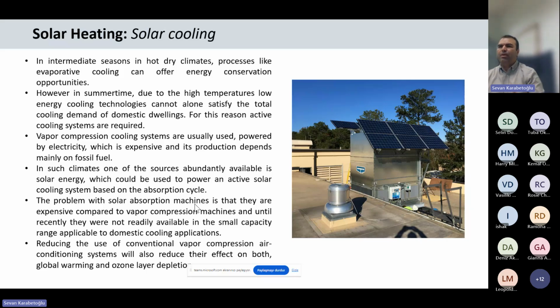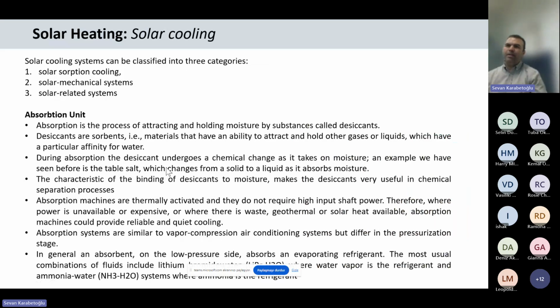Therefore, we can decrease the consumption of electricity for vapor compression, and the COP values for refrigeration will be higher by using these solar collectors. So, of course, reducing conventional vapor compression also reduces the effect of global warming and ozone layer depletion. So economically and environmentally it is a better solution. There are three types of solar cooling: solar absorption, solar mechanical, and solar related systems, but we will focus only on absorption units.